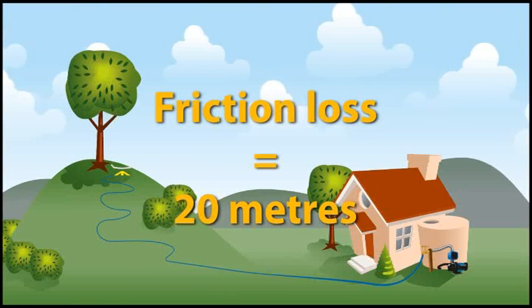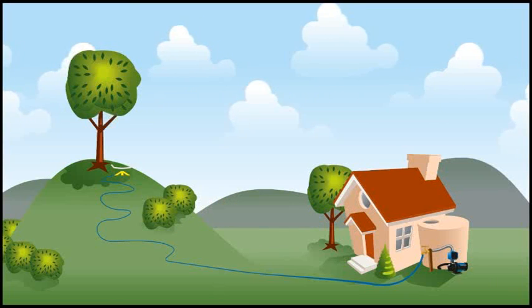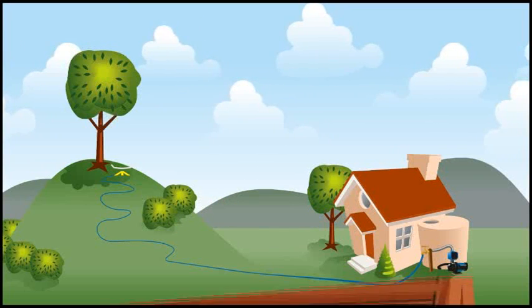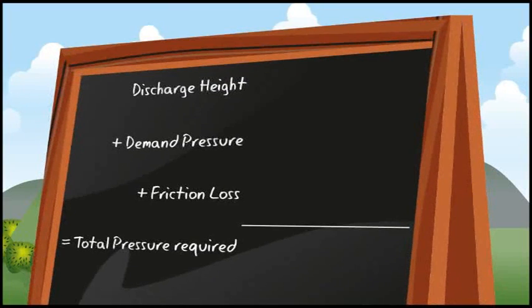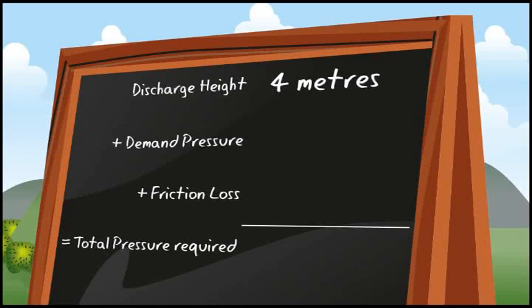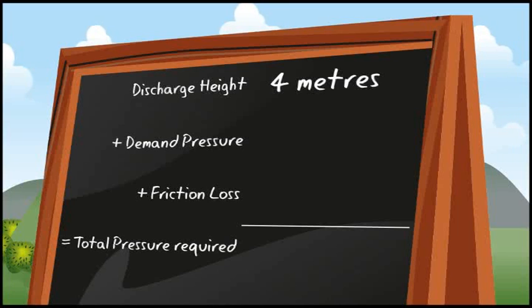The next step is to calculate the total head or pressure the pump will need to accommodate. We know that the discharge point is 4 metres above the pump, and the demand pressure of the sprinkler is 15 metres, or 150 kPa.